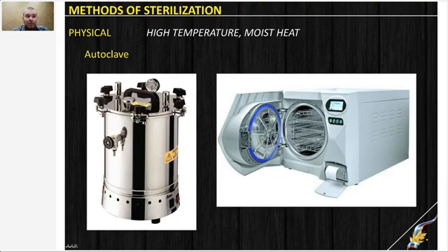Autoclaves can be of very different size. It can be small, as a simple boiler which is used to boil water, even at home, and it can be a very big and serious device, as is shown in the right part of the picture. It is a complex device with a built-in computer, and multiple parameters can be adjusted. You can adjust pressure, you can adjust time regimen, you can perform multiple steps of sterilization, and of course they can be very complex and very large in size.